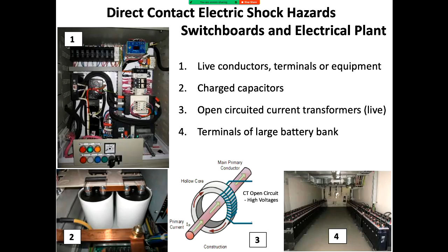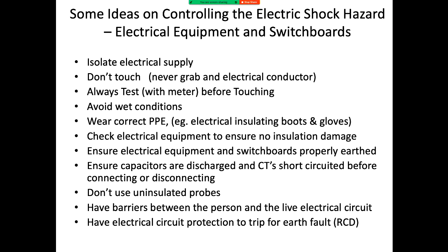So let's have a look at controlling the hazards. We've talked about them. I was going to get you to go through them. Obviously, the first thing that reduces the electrical hazard is to isolate the supply, and therefore there's no hazard. You've taken the hazard away. You always test before touching, and that's very important. Avoid wet conditions. Wear correct PPE. Check electrical equipment so there's no insulation fault, things are properly earthed, and things are discharged. And there are barriers, and you also have residual current devices, RCDs, and earth fault protection where you can.